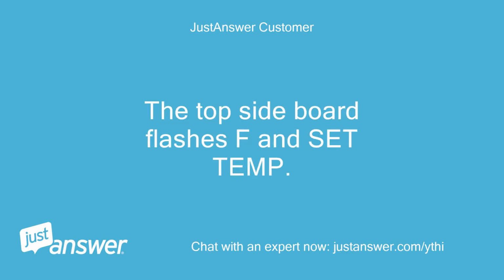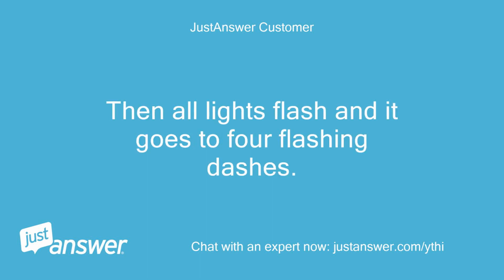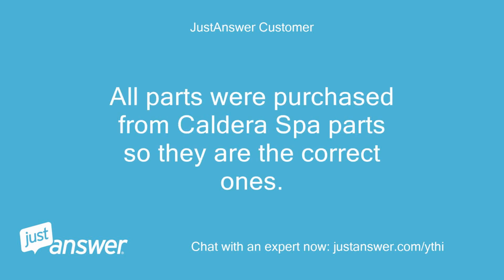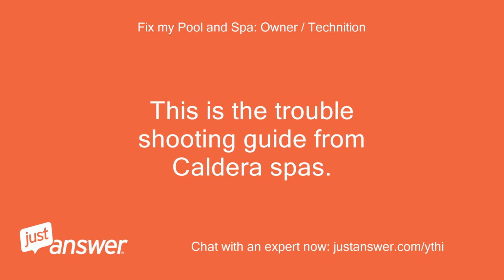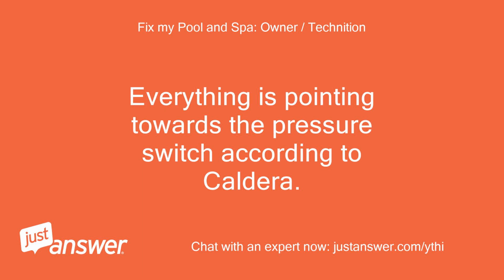The topside board flashes F and set temp. Then all lights flash and it goes to 4 flashing dashes. All parts were purchased from Caldera Spa parts, so they are the correct ones. This is the troubleshooting guide from Caldera Spas. Everything is pointing towards the pressure switch according to Caldera.